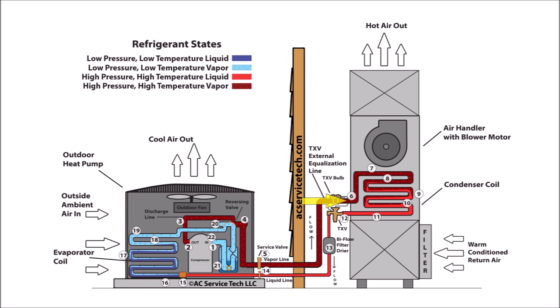At step six, the superheated vapor enters into the condenser coil where it starts to desuperheat while it's in vapor form. In step seven, we have the superheated vapor refrigerant rejecting heat and lowering in temperature — this is referred to as desuperheating. At step eight, the superheated vapor continues to reject heat until it has rejected enough heat to change into the saturated state, where liquid and vapor both exist at the same time. At step nine, we have the saturated refrigerant rejecting heat but not lowering in temperature.